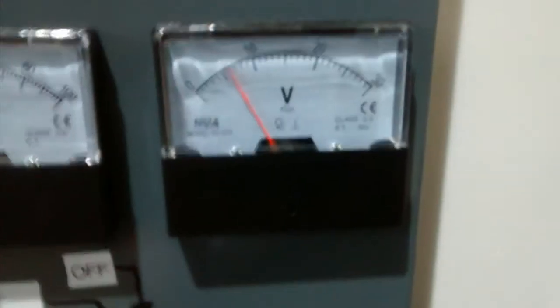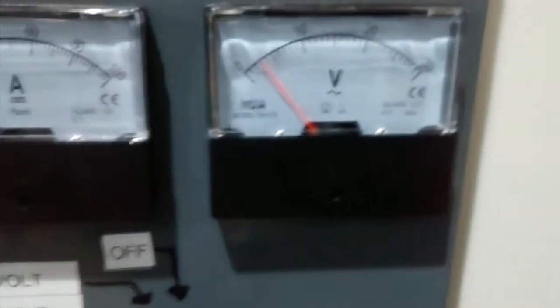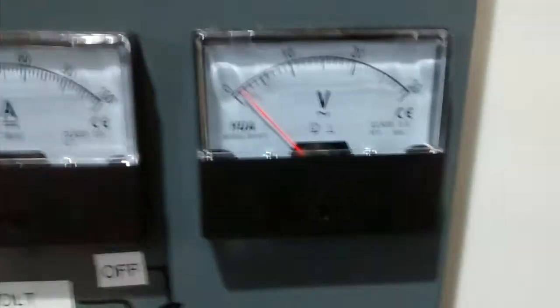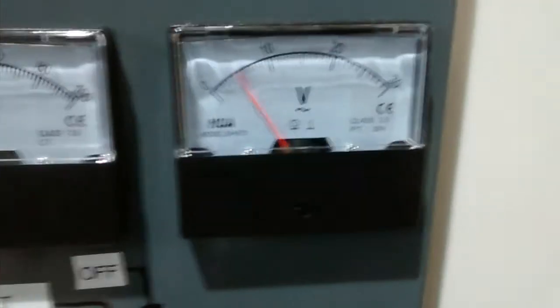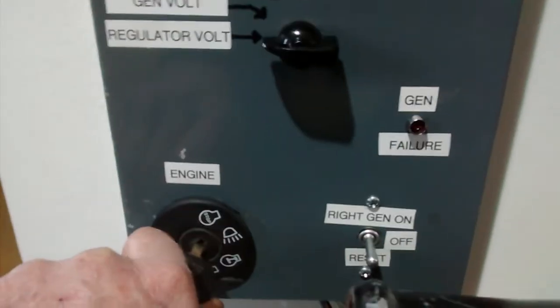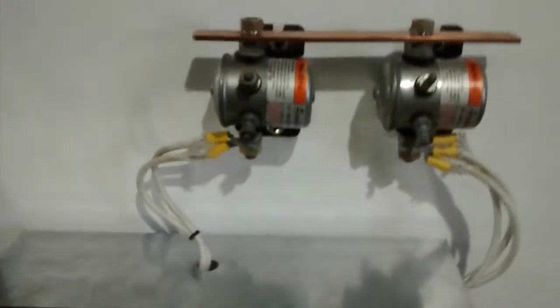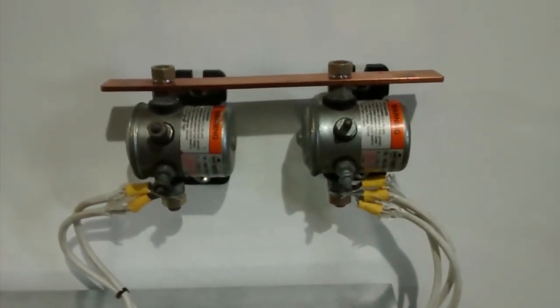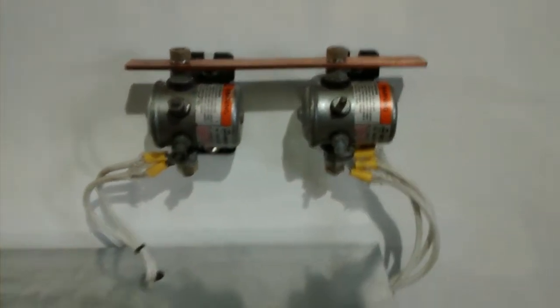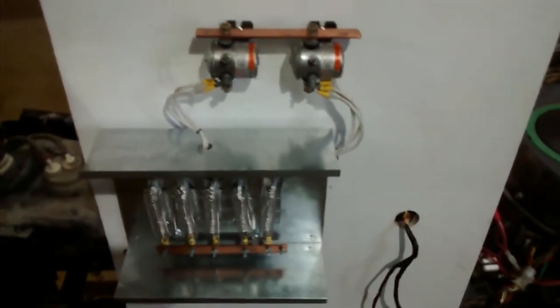So the back of the board here has a resistive load bank. These are electric dryer resistors, just bought them on Amazon, and they're connected to these two solenoid relays, contactors. Haven't hooked them up yet, but we'll be able to apply a load on the unit while it's running so we can check the reaction of the voltage regulator.